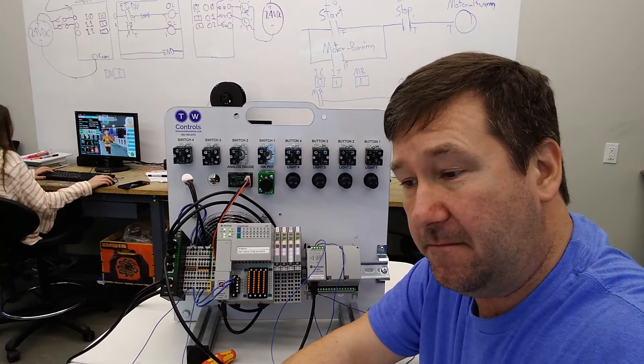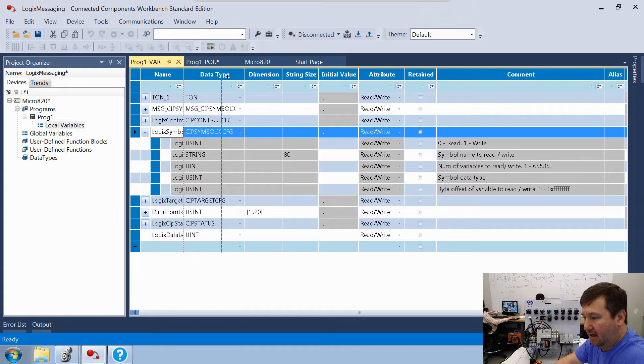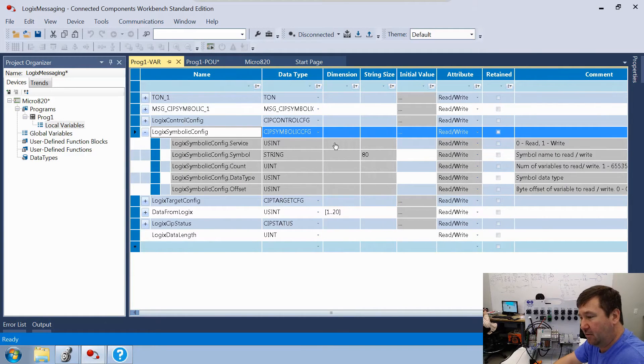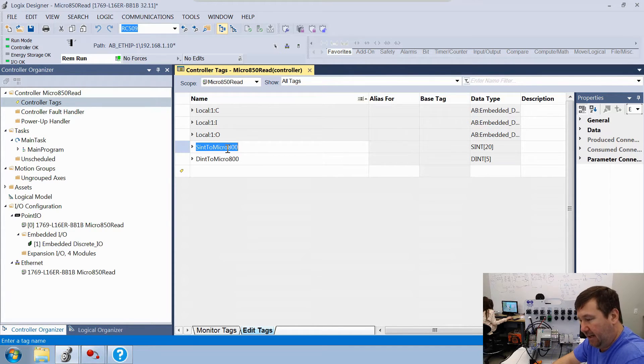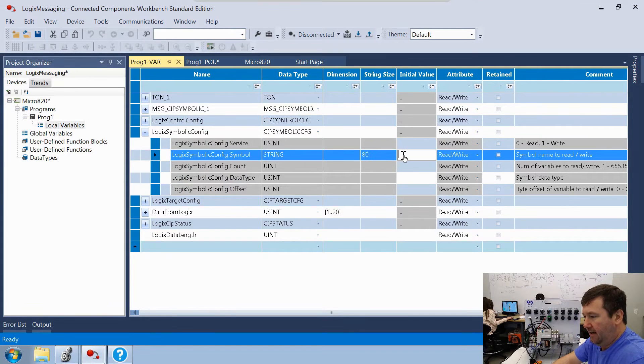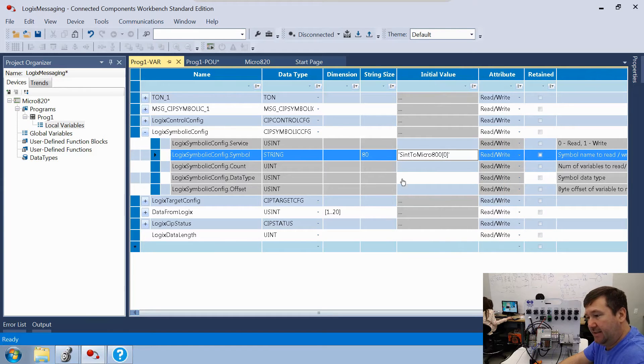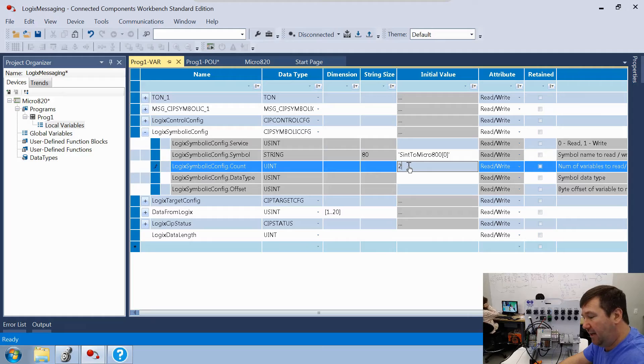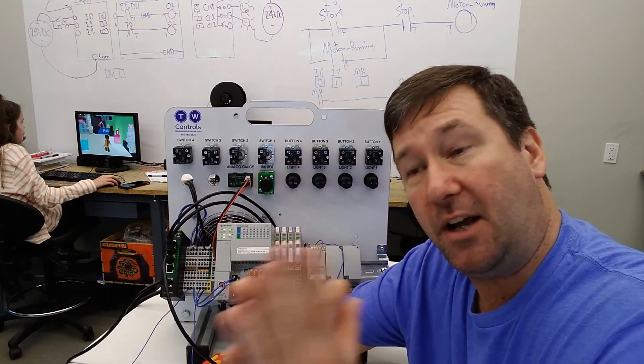Now a few of these tags need to be configured. Open the local variables and expand 'LogixSymbolicConfig.' The two main fields are the symbol and the count. The symbol is the data tag name in the ControlLogix or CompactLogix PLC — we called it 'SintToMicro800.' Copy that name and paste it here, then add '[0]' so it starts reading at the first data value.